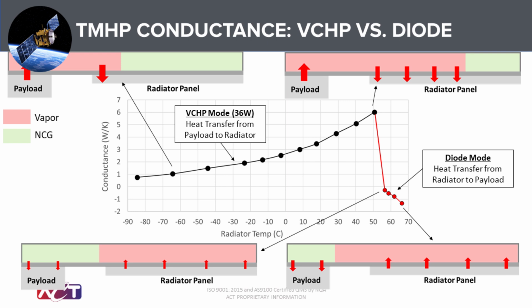Radiator temperature is on the abscissa, and on the ordinate axis is the conductance. As you see, now let's take a look at the upper left. For a colder temperature, from left to right, the second data point, where the arrow starts from, we have a sink temperature of approximately minus 65. We see the condenser opened a certain amount. If we go to the right, to the fourth data point, let's say minus 25, we see the condenser open more.